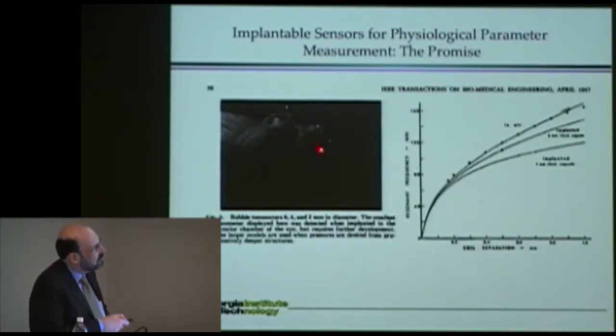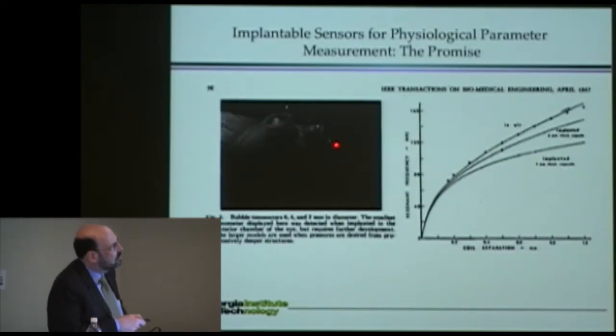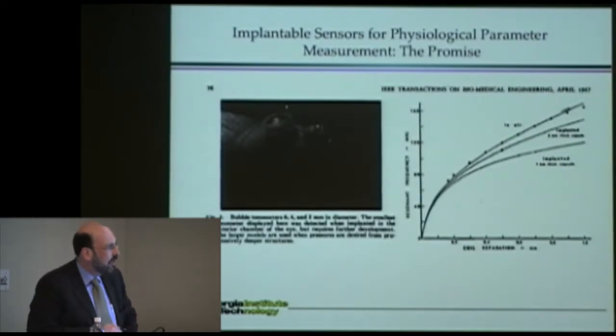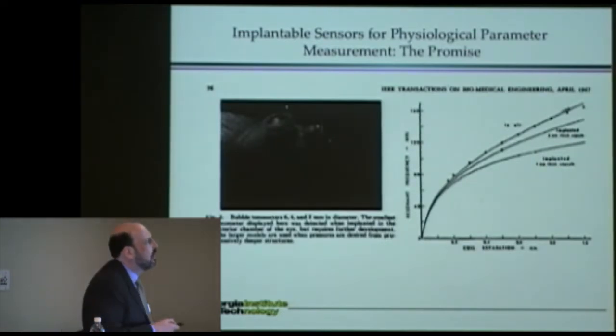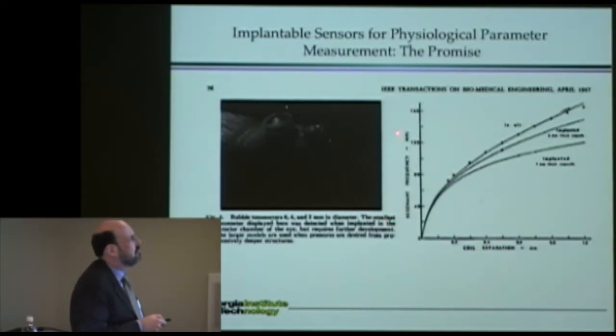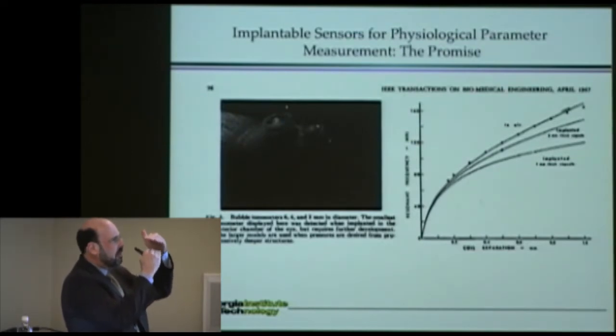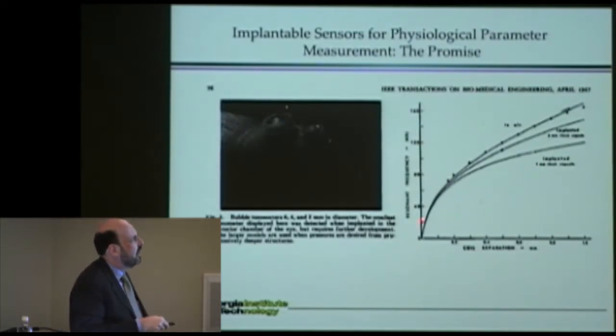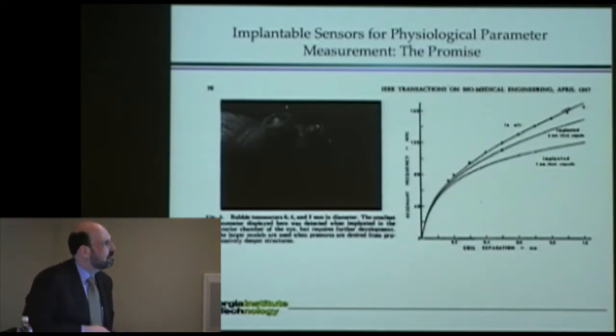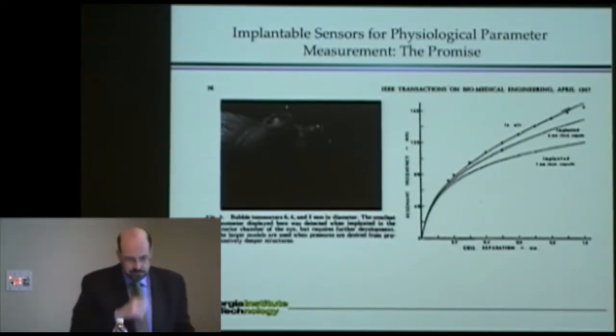So here's that same picture with the finger with the three little devices. The smallest one is 2 millimeters in diameter. The largest is 6 millimeters in diameter. And what I've shown here is a plot of the resonant frequency of this device in megahertz, between 0 and 160 megahertz, as a function of the coil separation, not quite the pressure, but the separation of the top and bottom pieces of this sensor. And you can see that you do trace out a curve, and therefore it can relate the frequency that you measure to the coil separation and therefore the pressure.